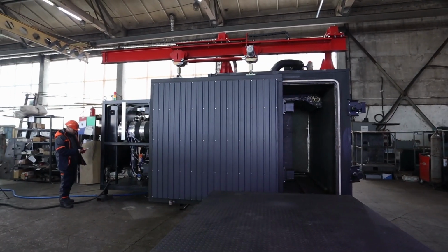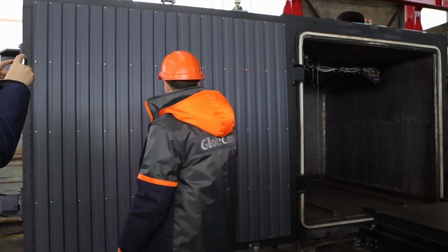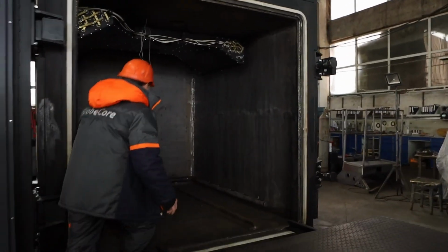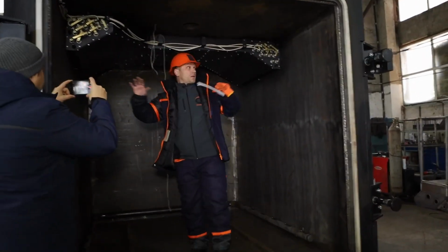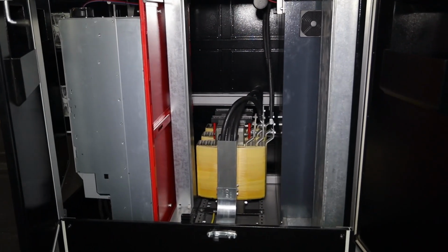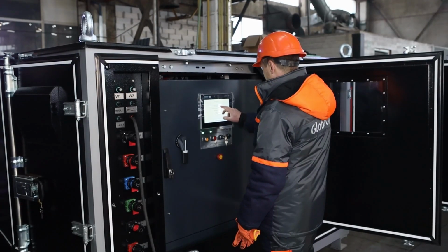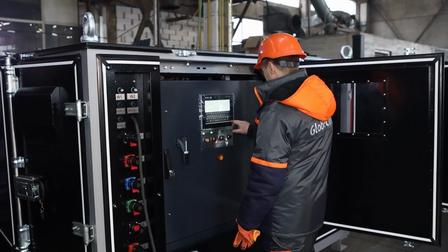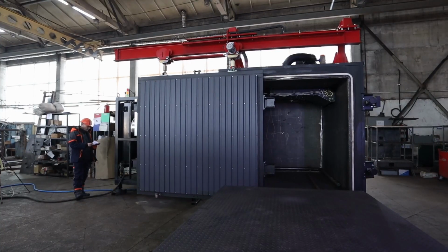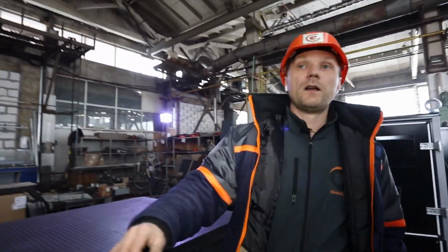Let's consider in greater detail how the drying process works. At the preparation stage, the transformer windings are placed in the vacuum oven, which means a controlled medium where the pressure and the drying temperature can be regulated. Next, the windings are connected to the low-frequency heating device that warms them up deeply and uniformly. Along with heating, a vacuum is created in the oven. The vacuum decreases the boiling point of water, which allows the water steam to evaporate at lower temperatures, ensuring the fast and efficient moisture removal.